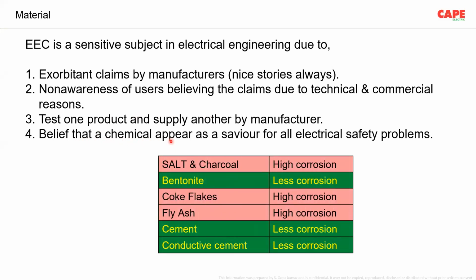And what are those materials practically sold in the market? The first one, salt and charcoal, everybody knows it because it is there in the standard. The second one is bentonite, which is a natural substance. Bentonite is a little bit less corrosive in comparison. The other material which is used is coke flakes. How does it look? It's like a flake. Flake means maybe 2, 3, 4 millimeters thick, a small paper-thin material having a diameter of something about 3, 4 millimeters, black in color. And this coke flake is used as an earth enhancing compound. Probably the resistivity of that material is 0.1 ohm meter or very much lesser, but actually it is highly corrosive. That is why it is written in IS 3043 that it corrodes.